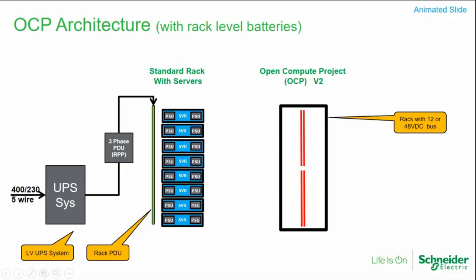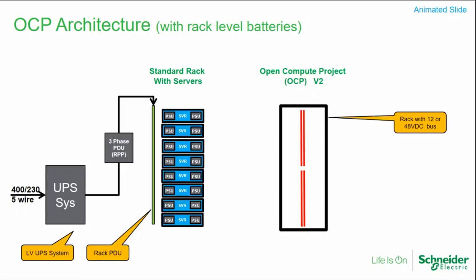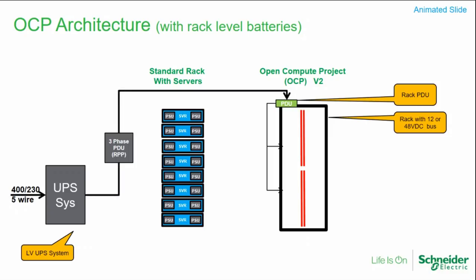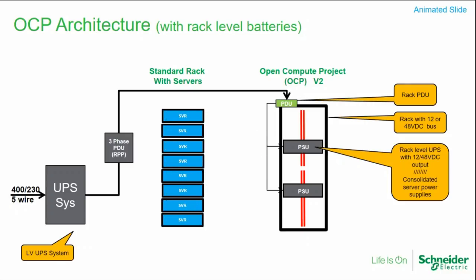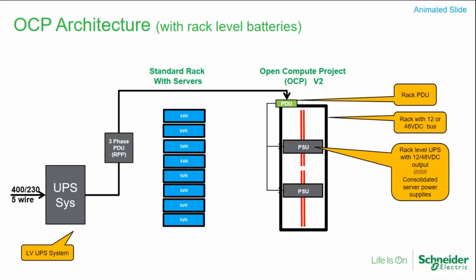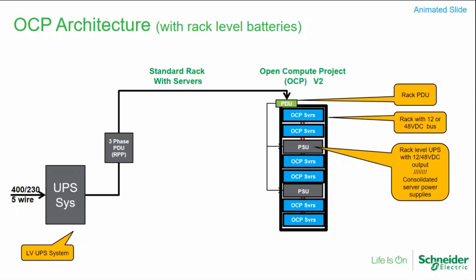So what's different? The rack is different — instead of 19-inch between the rails it's 21-inch. Also the PDU goes away and power is distributed to each server via bus bars in the back at 12 or 48 volt DC. To get the 12 or 48 volt DC, the power supplies are no longer in the servers — they're centralized. AC comes in and a rectifier gives you 12 or 48 volts. Whereas each server had two power supplies for redundancy, they now have none and it's all centralized at the rack. You can configure these for N+1, which is pretty typical with open compute, or still have 2N power to the overall PSU.